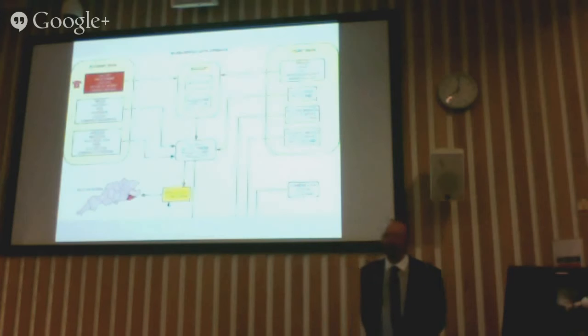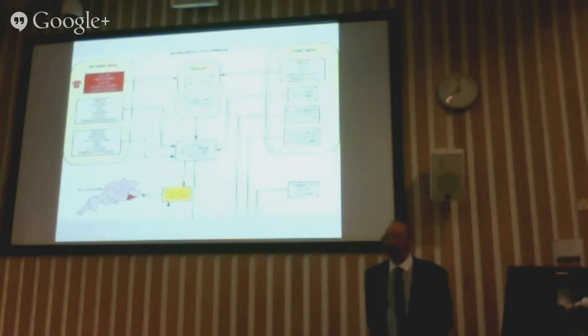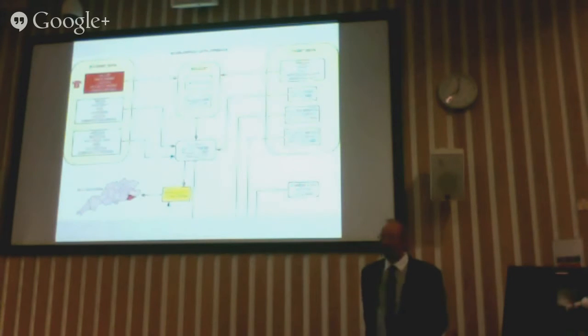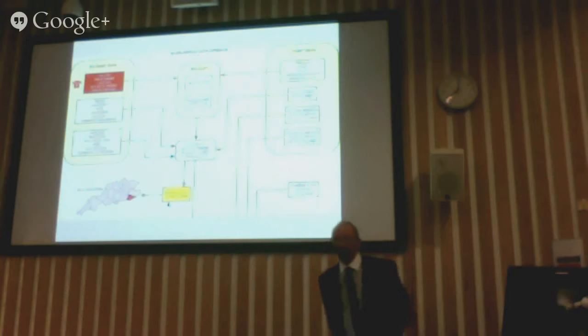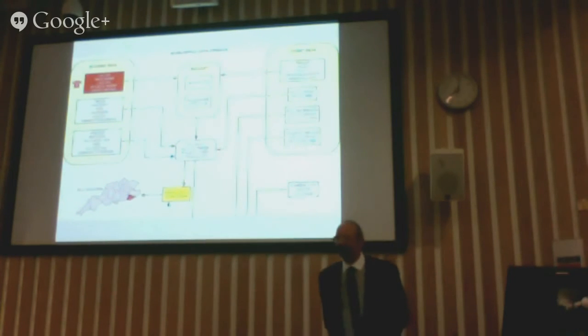And then, if that fails, we also have a good old-fashioned method. We phone a pager service with a code number, and in the station end electronics, we have a pager set up with just a pair of contacts, the vibrator contacts from the pager, connected with a piece of wire across a couple of contacts in the cabinet, and we just page, and it still fires off a message that says, communications failed, please call control, but it still rings the bells, opens the doors, puts the lights on, and alerts all the firefighters to come in. So, belt, braces, and a piece of string are there.